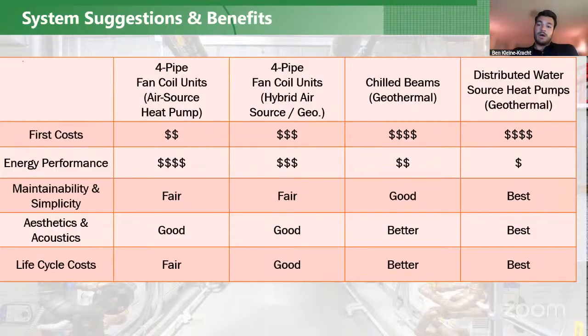If we lose our power, how are we going to freeze-proof the building? Okay, so a shelter-in-place situation, we would have to talk through whether that's what would happen here if the power went out. I'm not looking for occupancy, I'm looking for building survivability. And the typical answer with a heat pump system is, well, you run it off the generator.